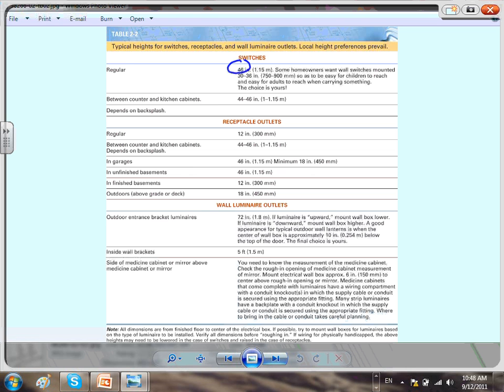Between counter and kitchen, here's the recommendation: receptacle outlets 12 inches on center. Between counter and kitchen, you can put in 44 to 46. In the garage, 46 inches above finished floor. Unfinished basement, 46 inches. Finished basement, 12 inches. Outdoor, 18 inches, though that will be plugged with all the snow here in Minnesota.